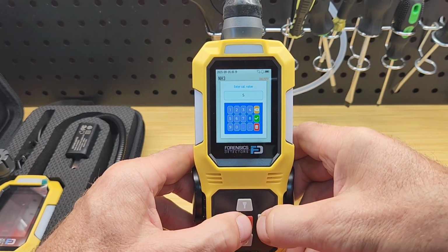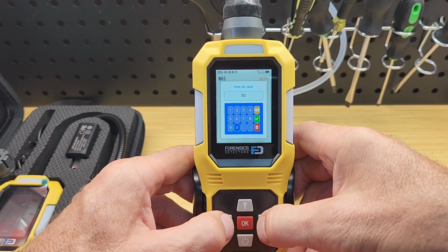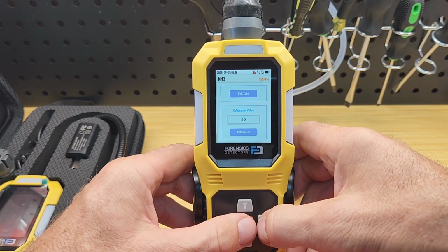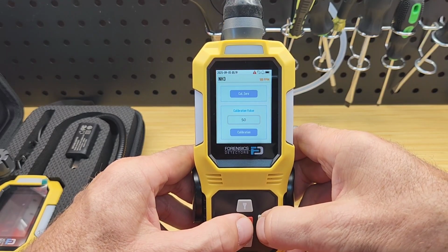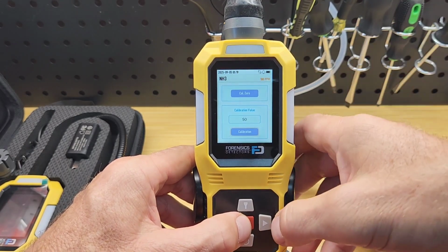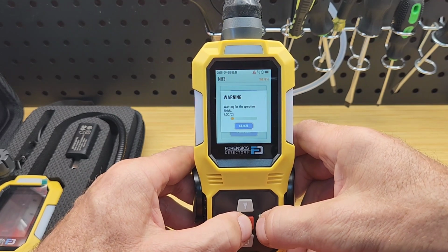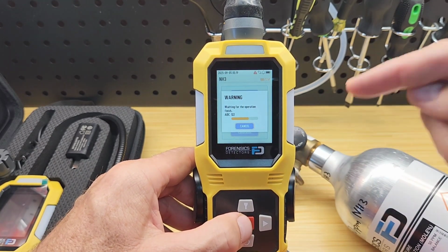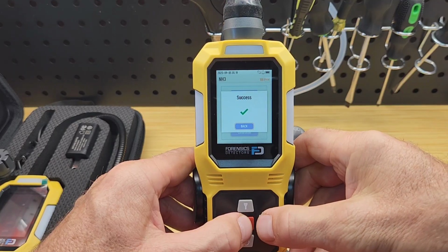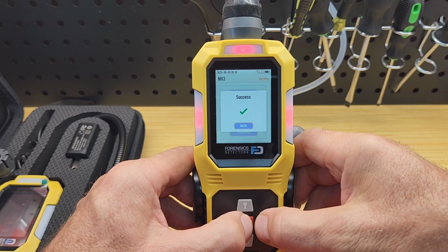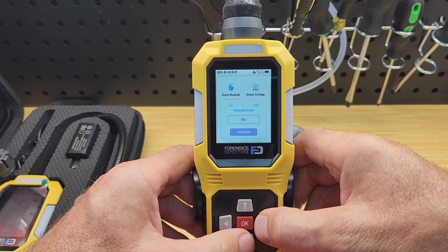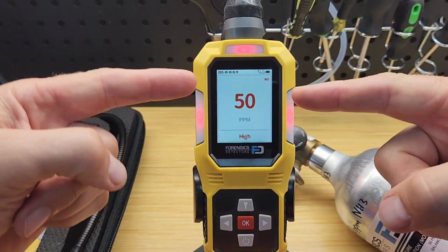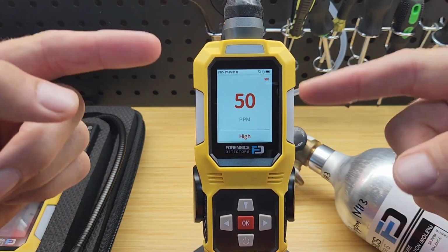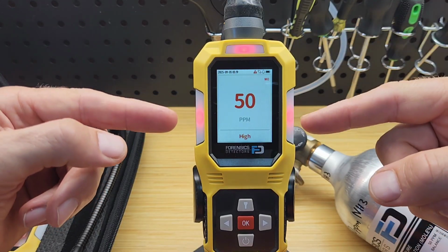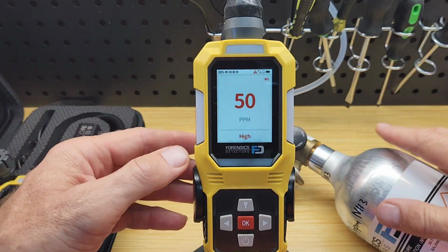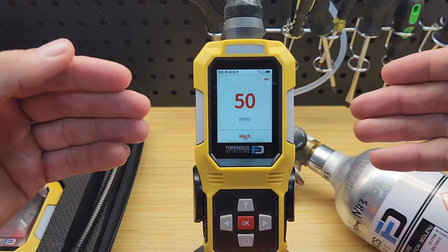Back. And then we have this nice keypad that we can enter. Let's go back to the yes. We got 50. And we're ready to press the calibration button. Calibration. I've waited over 2 minutes now. It's stabilized. I'm going to press calibration. And it's going to force it to 50 parts per million. Bang. Done. I'm going to press back. We're going to go back. And it's 50. Bang, the unit's been calibrated. It was old, it aged, the output voltage from the sensor decreased, and it was time for a calibration. I performed calibration and bang, there you have it.